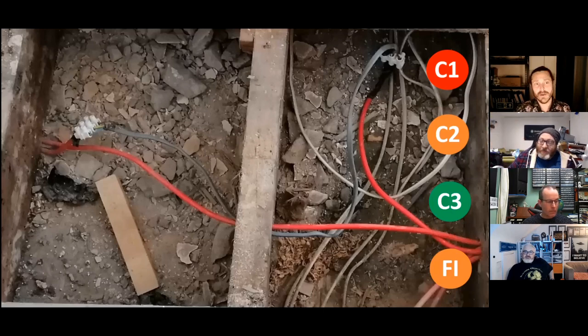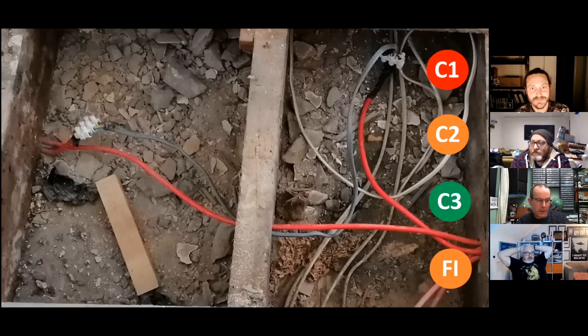Okay, so yeah. Dave, if there was a fire in this room, bear in mind this might be a circuit for a sounder that could be doing a large proportion of the building. It could be a sleeping risk. This could be an HMO, for example. There's a flaming inferno in this room. Do you think within the void it's going to heat up? Oh, yeah. Well, Jonathan, it is an HMO, so that's exactly what it is. It's a six bedroom HMO. C1 then.